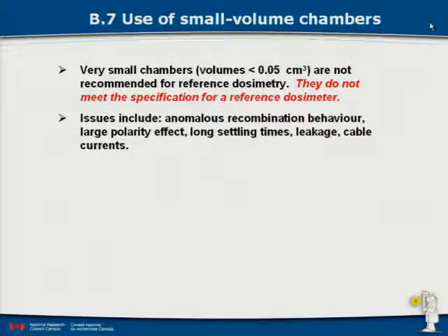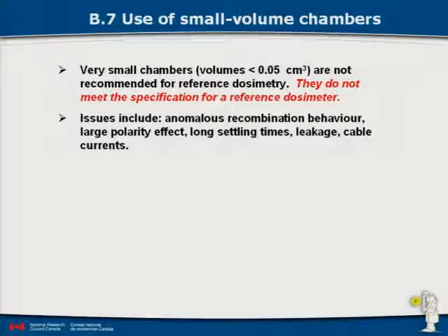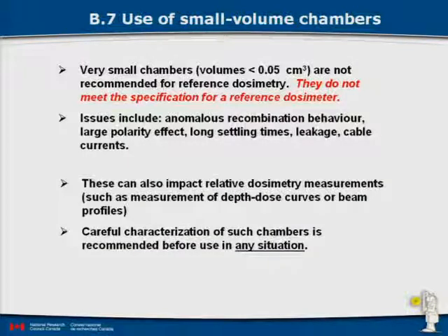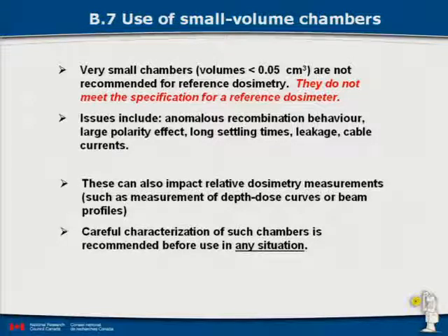Regarding small-volume chambers — microchambers of less than 0.05 cc — they're not recommended for reference dosimetry because they don't meet the specification. Not all chambers have all issues, but collectively they all have at least one anomalous behavior. For small fields, some of those effects will impact relative dosimetry, so when using these chambers in relative dosimetry you still need to consider their performance characteristics.